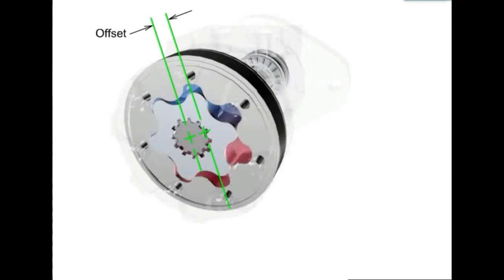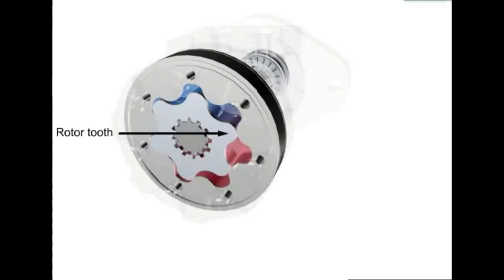The rotor sits offset in the cavity of the stator. An open cavity between the rotor and the stator is created by the offset of the rotor, which has one less tooth than the stator. One tooth of the rotor is always opposed to one tooth of the stator. The cavity is divided into two pressure zones by the opposing teeth. One side of these opposing teeth is high pressure and the other side is low pressure.